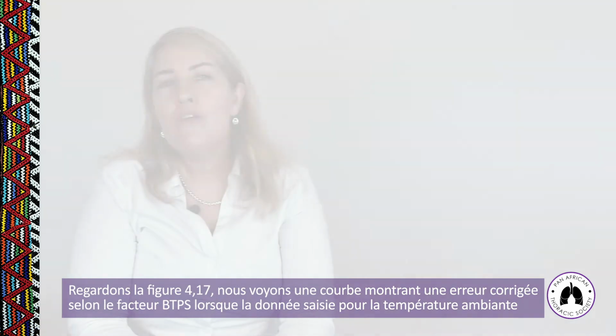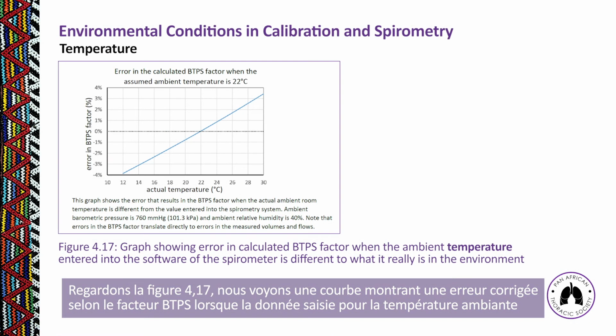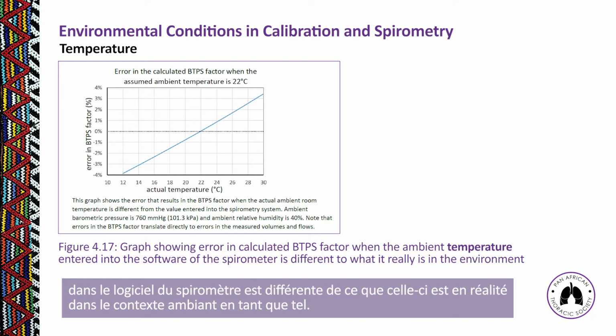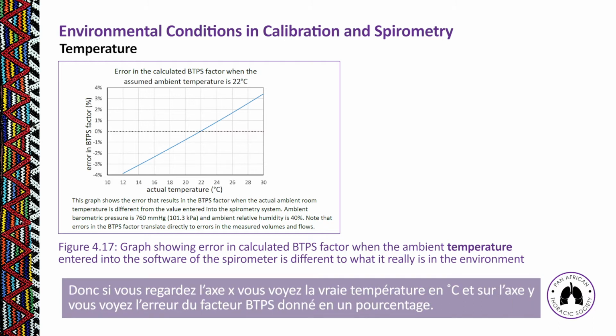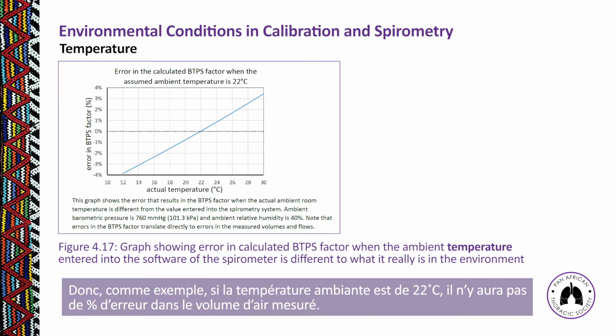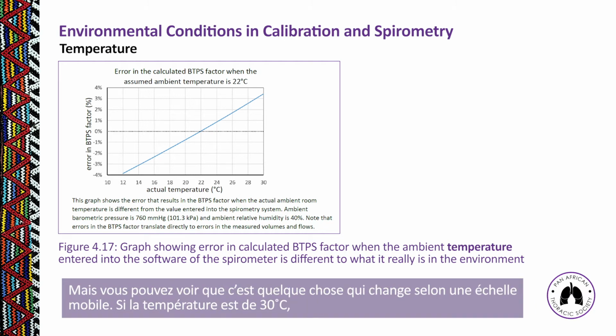If you look at figure 4.17, you can see a graph that shows error calculated in the BTPS factor when the ambient temperature entered into the software of the spirometer is different to what it really is in the environment itself. So if you look at the x-axis, you're looking at the actual temperature in degrees Celsius. And if you look at the y-axis, you're looking at the error in the BTPS factor as a percentage. So for example, if the ambient temperature is 22 degrees Celsius, there will be no percentage error in the volume of air measured. But you can see then how this changes on a sliding scale.